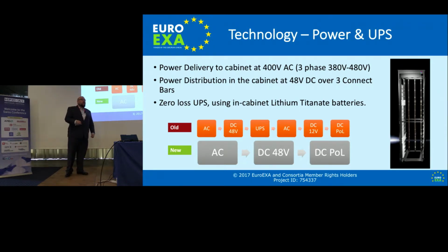Did you know that if you double the voltage, you quarter your electrical losses for transmission of energy? So by going from 12 volts to 48 volts, the electrical losses are reduced by a 16th for that transit distance. By taking the 48 from the power supply all the way into the daughter board and electronics, that reduced the electrical losses, which we normally would just ignore. We wouldn't see it, but it's quite substantial for 12 volts going across a motherboard.